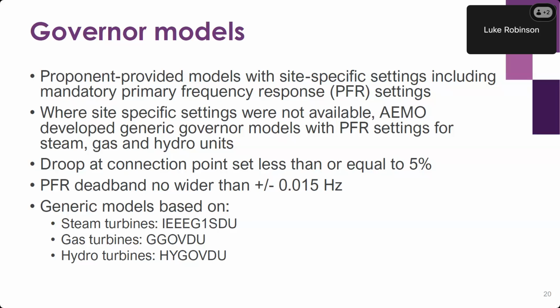To manage this issue, AEMO has developed generic governor models as part of the 2022 PSFRR process to represent typical steam, gas, and hydro turbine frequency responses. These models were used in the PSFRR and GPSRR studies for units where the generator supplied governor models don't have the updated PFR settings in the OPDMS, or AEMO does not have a governor model in the OPDMS. So by developing these generic governor models, a more realistic and consistent approach can be used. And we can ensure that the correct PFR settings that meet the primary frequency response requirements could then be implemented.